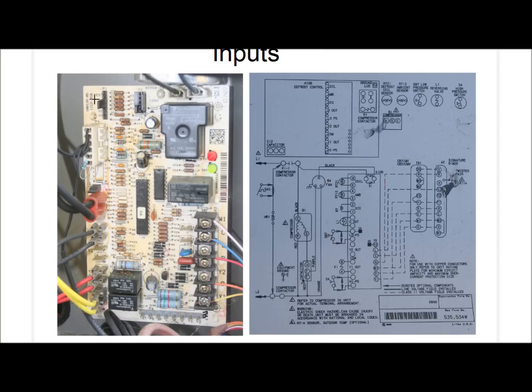Now let's talk about the line voltage input. And that is right here up on the control board, top right. And that is one leg of the 230 volts. And if you look on the schematic, this terminal up here on the top right of the control board is designated by this circle right here on the schematic diagram. So this is a 230 volt input to the control board.